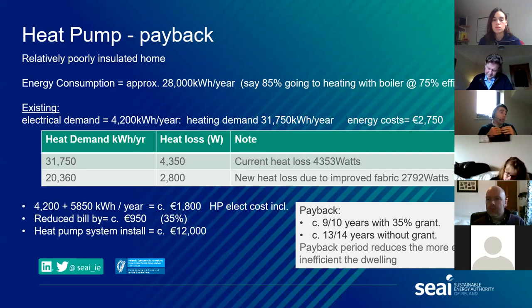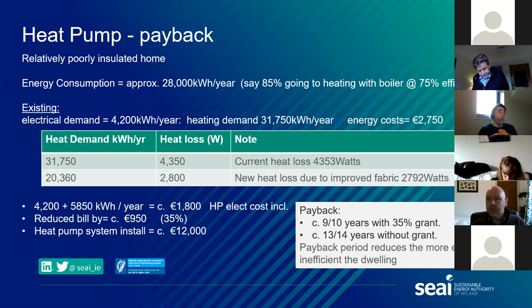Looking at the fabric and heat losses, and implementing fabric and attic insulation, you're bringing your heat loss down to 2,800 watts and reducing your heat demand to 20,000, as shown in the table. If you divide that by the energy efficiency of a heat pump, your overall kilowatt hours per year comes down to around the 10,000 mark.